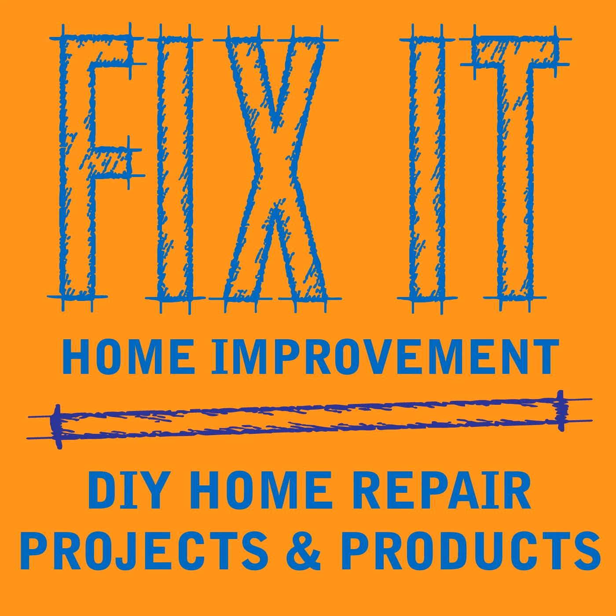Another thing, if you have an older furnace and you have a noisy motor or there's no air moving, you probably have a broken belt, and these go bad. Again, these might last a little longer, but they do go. They start to crack and wear out. I would also have a spare belt, and you want to check the number stamped on the belt and get an exact match. You want that tight.